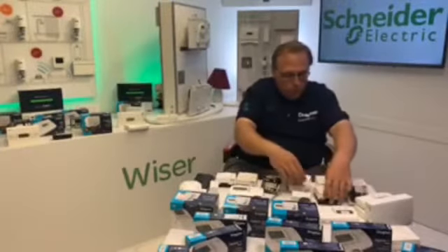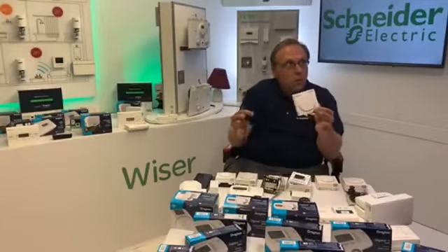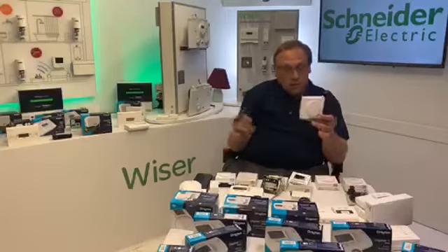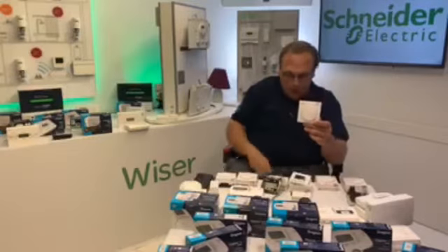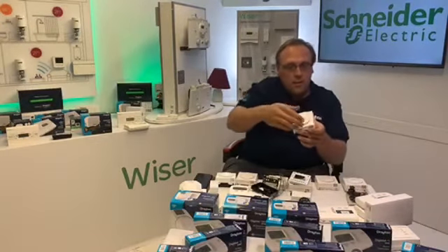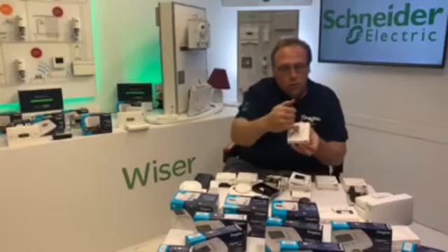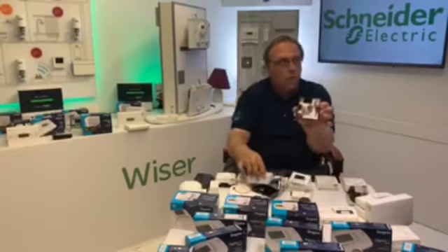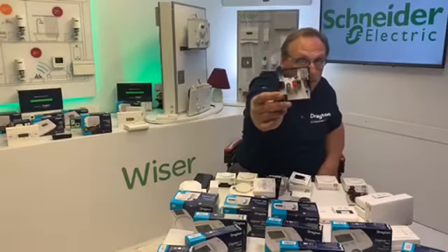We then come on to one which is a bit of an oddball, which is the RTS8. It's also known as a Digistat, and this is the only one in the RTS range that doesn't share that industry standard backplate. That's got a completely different backplate. That's actually like a pattress. That's to stand it off of the wall. And then to get into this, you don't undo the screws at the bottom. You take off the cap, you undo the screw, and then the face comes off completely. So you can see the backplate on that is essentially a PCB.